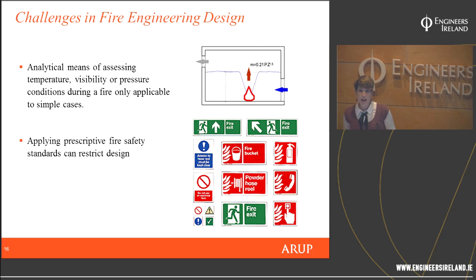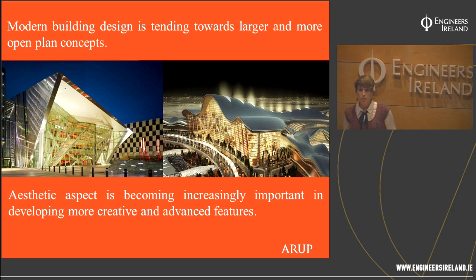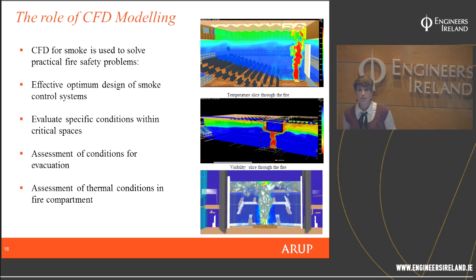You have to consider buoyancy — the variation in smoke density due to differential temperature — and pressure from wind, air velocity within the building, and the ventilation system. There are analytical methods that help understand how much smoke a fire will produce depending on fire size or load. However, these calculations are not enough on their own. Prescriptive codes tell you how to contain smoke and fire within a certain area, but following those guidelines would prevent us from having the amazing open-plan buildings we have today.